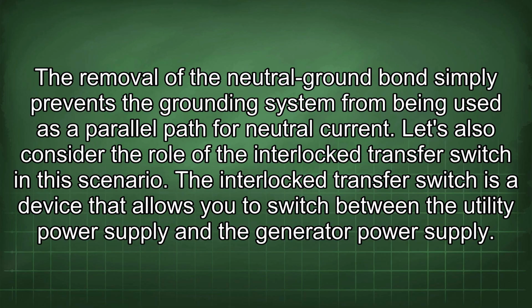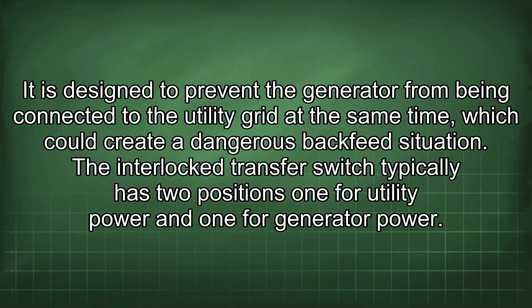The interlock transfer switch is a device that allows you to switch between the utility power supply and the generator power supply. It is designed to prevent the generator from being connected to the utility grid at the same time, which could create a dangerous backfeed situation.